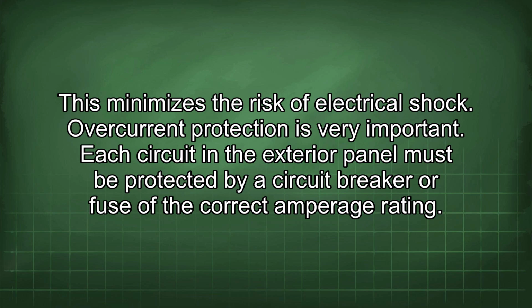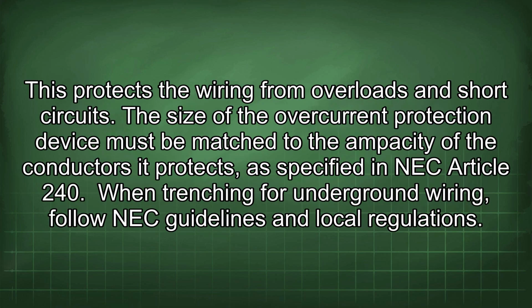Overcurrent protection is very important. Each circuit in the exterior panel must be protected by a circuit breaker or fuse of the correct amperage rating. This protects the wiring from overloads and short circuits. The size of the overcurrent protection device must be matched to the ampacity of the conductors it protects, as specified in NEC Article 240.